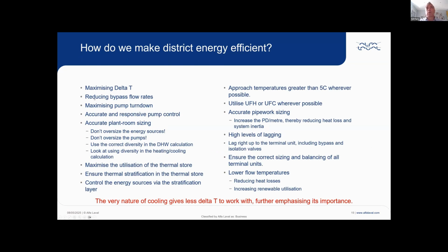So we need to think about bypasses on the network. We need to reduce them as much as we possibly can. We realize that they are required in certain instances, but we need to keep the number to a minimum. We need to valve control those bypasses with the right valve. And very often I see the wrong kind of valve used, or the right valve that's just not being commissioned properly. So that's absolutely key. We need to maximize the control range of the pump, so it speeds up to hit peak demand, but then backs down to its lowest position possible at times of low demand.